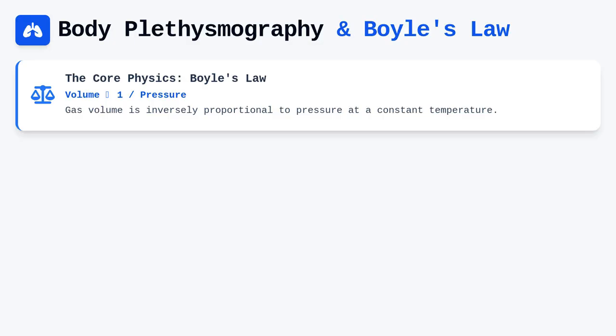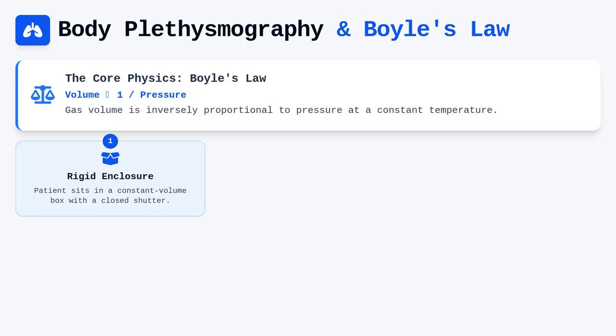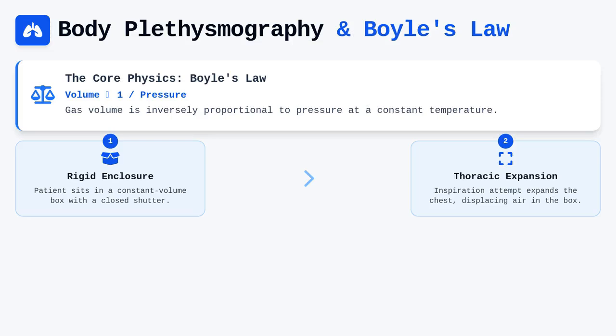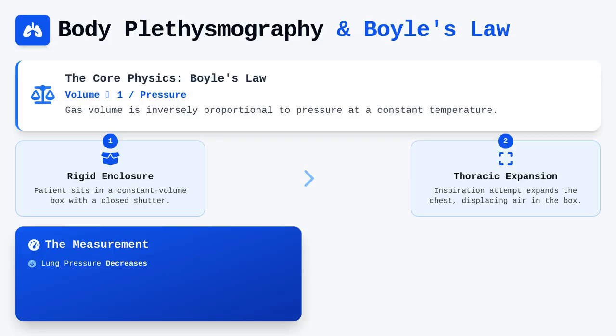At the core of all body plethysmography resides the physical manifestation of Boyle's law, which dictates that the volume of a gas is inversely proportional to its pressure at a constant temperature. In a constant volume variable pressure plethysmograph, the patient sits inside a rigid enclosure while the box pressure is monitored as the patient makes respiratory efforts against a closed shutter. As the patient attempts to inspire against this closed airway, the thoracic gas volume expands, causing the lung pressure to decrease and the box pressure to increase accordingly.